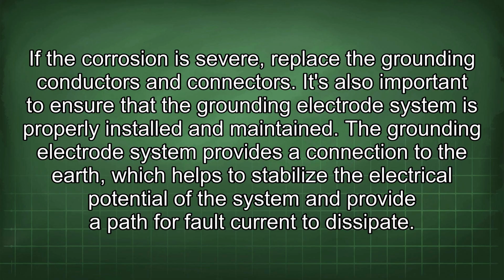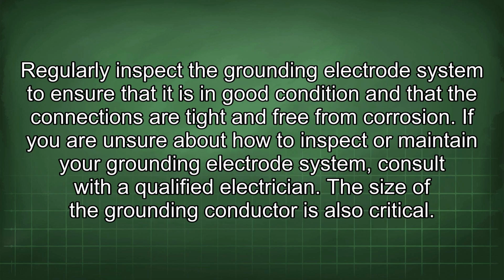It's also important to ensure that the grounding electrode system is properly installed and maintained. The grounding electrode system provides a connection to the earth, which helps to stabilize the electrical potential of the system and provide a path for fault current to dissipate. Regularly inspect the grounding electrode system to ensure that it is in good condition and that the connections are tight and free from corrosion. If you are unsure about how to inspect or maintain your grounding electrode system, consult with a qualified electrician. The size of the grounding conductor is also critical.